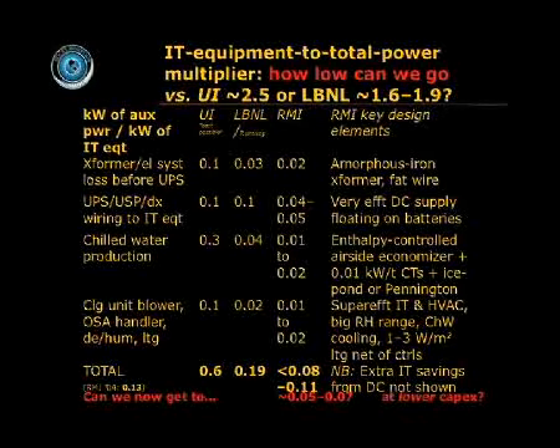Well, you'd cut your electric upstream supply overhead down to 2% by using amorphous iron transformers and fatter wire. Copper's cheaper than kilowatt hours. And then you would use a very efficient direct current bus floating on batteries or on a flow battery. Then for your chilled water production, you would use an enthalpy-controlled airside economizer, the 0.010 kilowatt per ton cooling towers for water-side economizer, and a desiccant-driven cycle in your climate.